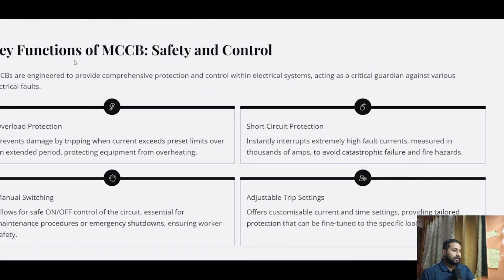Then we will see the key functions of MCCB, that is safety and control. MCCBs are engineered to provide comprehensive protection and control within the electrical system. They act as a critical guardian against various electrical faults. So first we will see how it provides overload protection. It prevents damage by tripping when the current exceeds the preset limits over an extended period, protecting equipment from overheating. So here we can preset the limits of current. If the current exceeds this preset value, then the MCCB will trip.